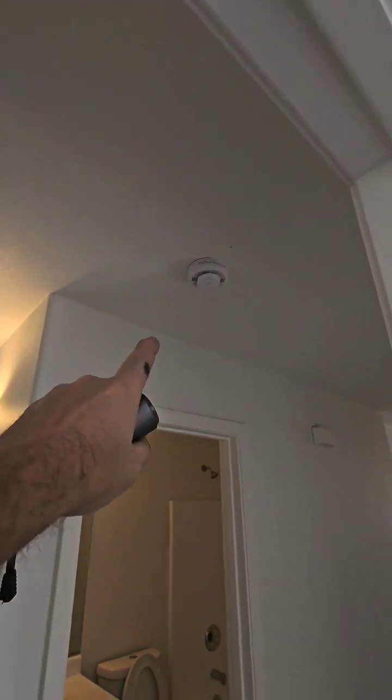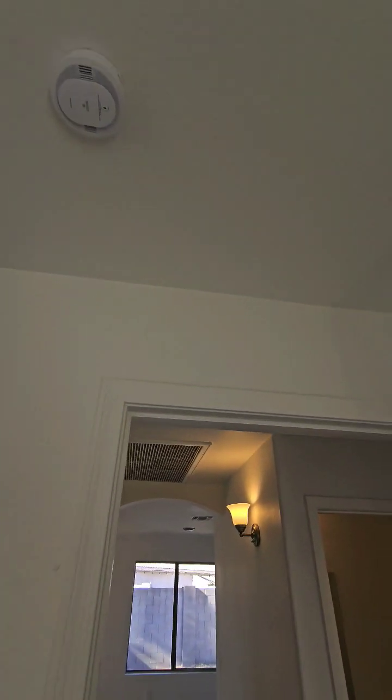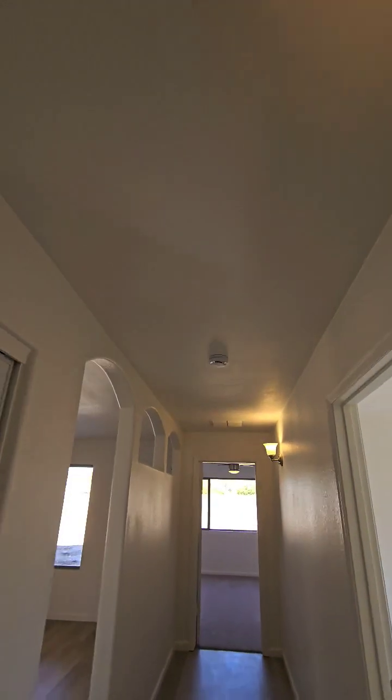They did go ahead and update your smoke detectors — smoke detectors in the hallways, and ran some smoke detectors in the bedrooms too. These are all battery operated, so they don't interconnect. If one goes off, the next one won't go off.